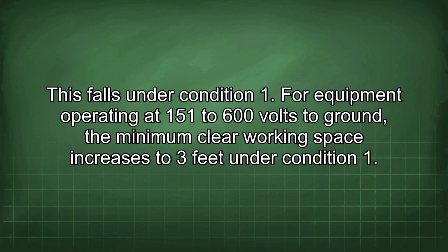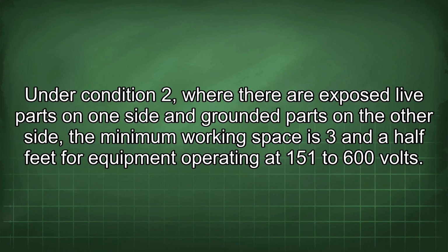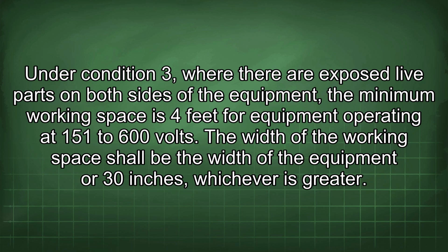For equipment operating at 151 to 600 volts to ground, the minimum clear working space increases to 3 feet under Condition 1. Under Condition 2, where there are exposed live parts on one side and grounded parts on the other side, the minimum working space is 3.5 feet for equipment operating at 151 to 600 volts. Under Condition 3, where there are exposed live parts on both sides of the equipment, the minimum working space is 4 feet for equipment operating at 151 to 600 volts.